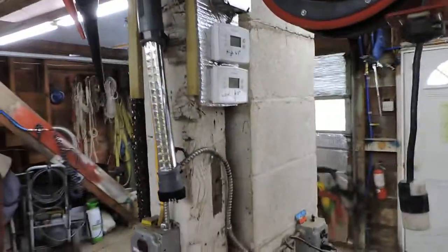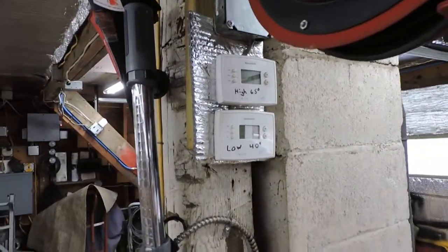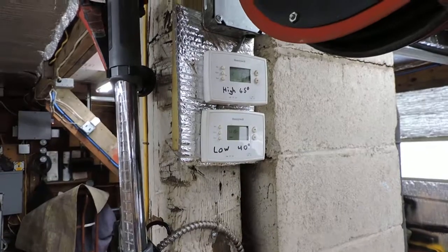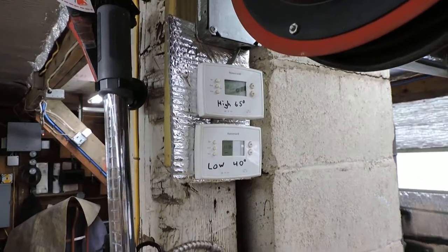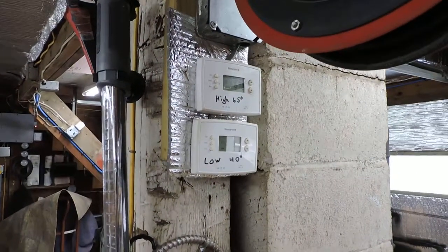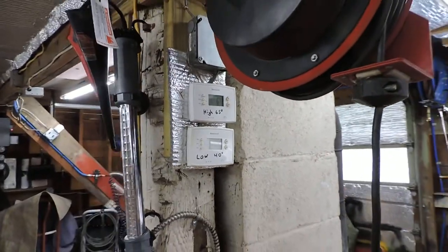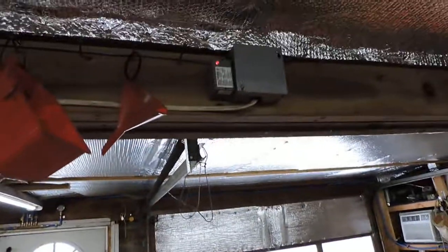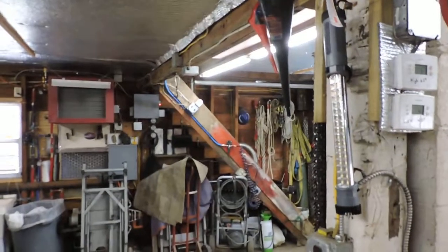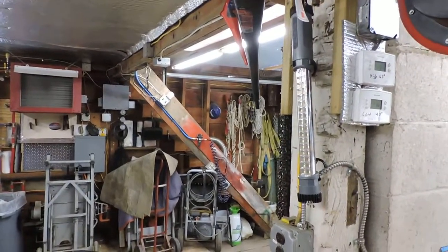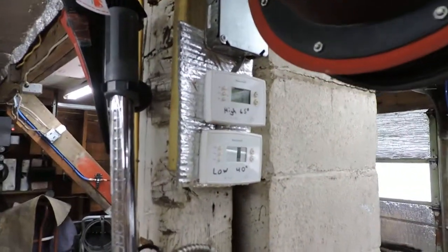The nice thing about this is there's a default thermostat in here. We've got two thermostats, a high and a low. The bottom one defaults to 40 degrees and the top one is 65. And the top one is in parallel with this relay that's off the lighting. So when anybody walks in, the motion sensor turns on the lights automatically, and that tells this high thermostat to turn on. So that thing will cycle out.